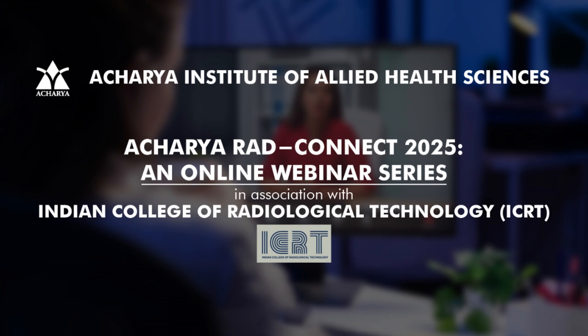Always, the first preference is diagnostic accuracy of the images. So we cannot say that if a patient has come, we will give 80 kVp and 100 mAs. That cannot be done. By looking at the patient itself, you have to adjust the KVP. Usually, KVP is adjusted by you, and MAS will be adjusted by the equipment.